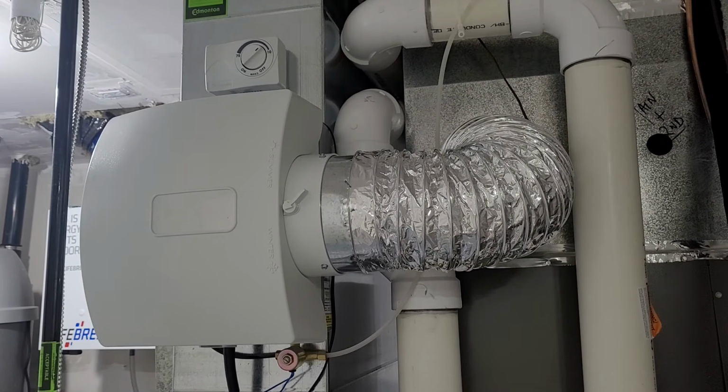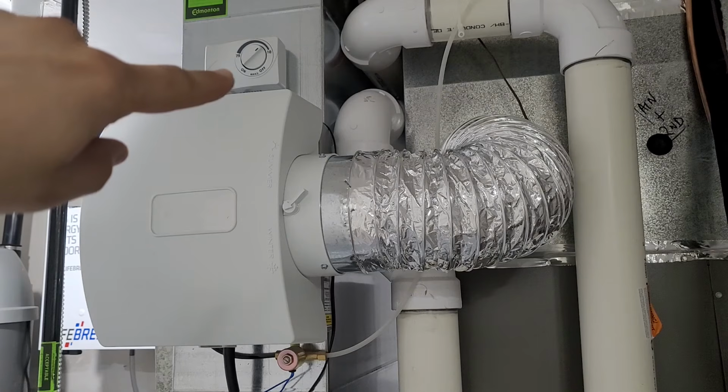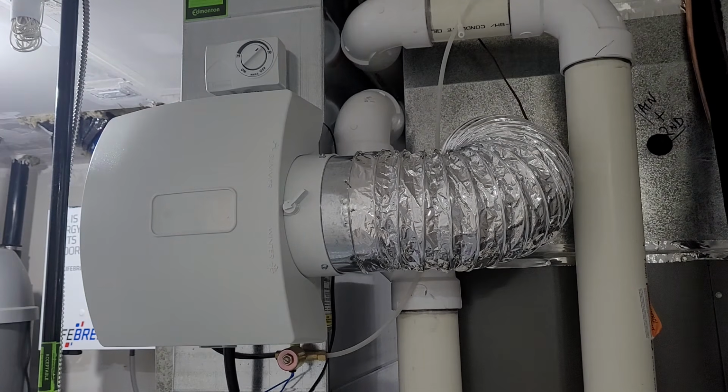Now, the second method to reduce your humidity is to set down the humidity setting on your humidifier. So usually what happens is, sometimes I get a call and I go and inspect, and the homeowner is doing very good ventilation for their house, but still their humidity is not going down. So in that case, the reading on the humidistat is set to a higher level. So as soon as your humidity drops down, there's a sensor that takes the reading every time air passes through. And if the sensor reads that humidity is low in the house and the setting is higher, it starts the water.